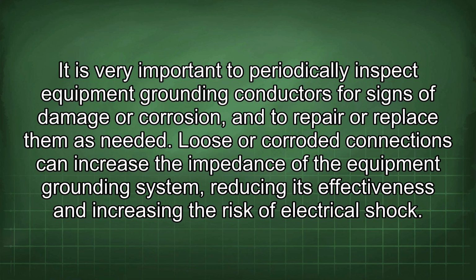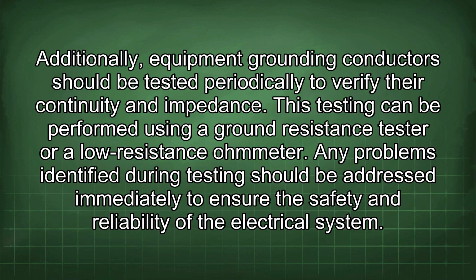Loose or corroded connections can increase the impedance of the equipment grounding system, reducing its effectiveness and increasing the risk of electrical shock. Additionally, equipment grounding conductors should be tested periodically to verify their continuity and impedance. This testing can be performed using a ground resistance tester or a low resistance ohmmeter. Any problems identified during testing should be addressed immediately to ensure the safety and reliability of the electrical system.